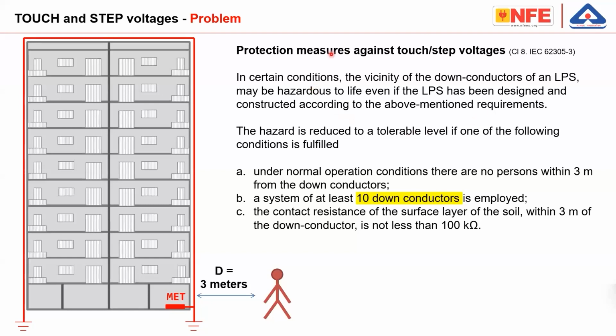You can see these wordings in IEC 62305 Part 1, Part 3. Of course, in certain conditions, the vicinity of down conductors of an LPS may be hazardous to life, even if the LPS has been designed and constructed according to the above-mentioned requirements. The hazard is reduced to a tolerable level if one of the following conditions is fulfilled. Under normal operation conditions, there are no persons within 3 meters from the down conductor. So your building is well protected, but from the down conductor, a chance of an accident to a person outside the building exists. So you must keep 3 meters away from the down conductor.